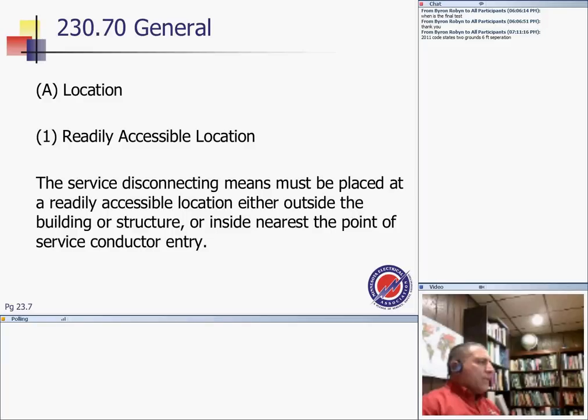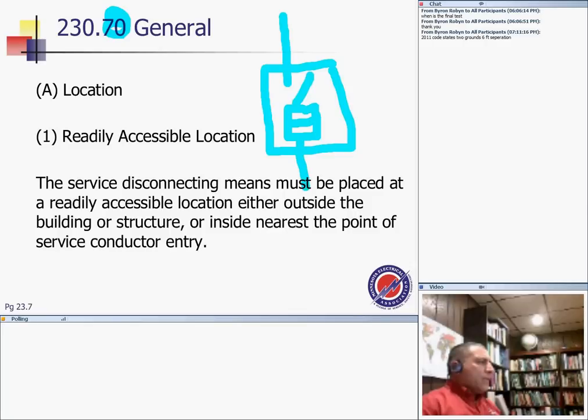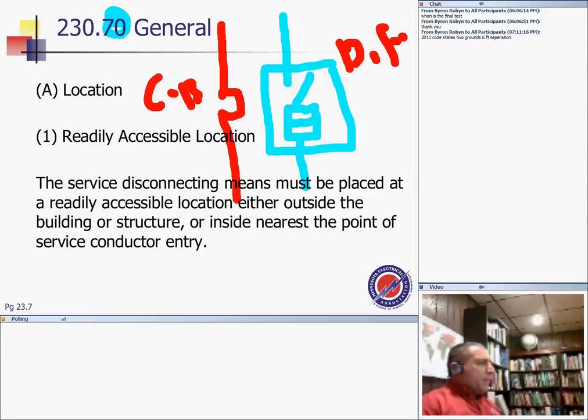Basically, location: readily accessible disconnect. This is for the disconnect, guys. With the power lines, I hope by now we all know, as you bring your power lines in, they have to be connected directly to what we call a disconnect. And a disconnect must have a fuse. So I have a fused disconnect like this. Or, like a lot of us do instead of this, you can use an overcurrent protection device, a circuit breaker. So here's my circuit breaker. I have a disconnect fused with a fuse disconnect. The disconnect means must be placed at a readily accessible location, either outside of the building or structure, or inside at the nearest point of entrance.